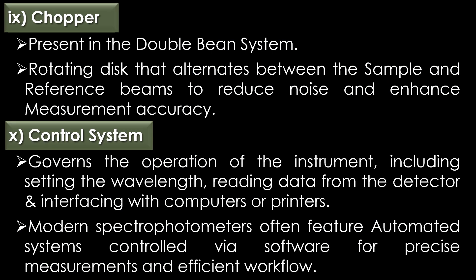Chopper: the chopper is present in the double beam system. It is a rotating disc that alternates between the sample and reference beams to reduce noise and enhance measurement accuracy. Control system: the control system governs the operation of the instrument, including setting the wavelength, reading data from the detector, and interfacing with external systems like computers or printers. Modern spectrophotometers often feature automated systems controlled via software for precise measurement and efficient workflow.